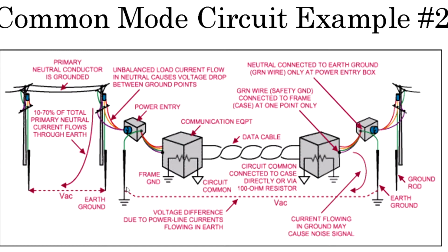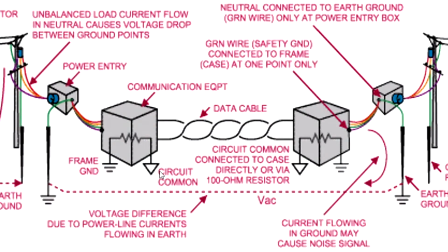Well, as that current flows through the earth, there's a voltage gradient developed along the ground. If you remember earlier, I said that ground rods are not at 0 volts with respect to each other. Each ground rod is at a different potential. So those of you who might be working in the industry, telephone offices, you might recognize this drawing, or at least the circuit. It's showing how the outside influences are pushing a current through this whole system. Here we've got two different buildings, data and telemetry cable going between them, and their earth potentials are at different voltage potentials. So basically you've got a battery between these two pushing common mode currents. Okay, the next example should bring it home.